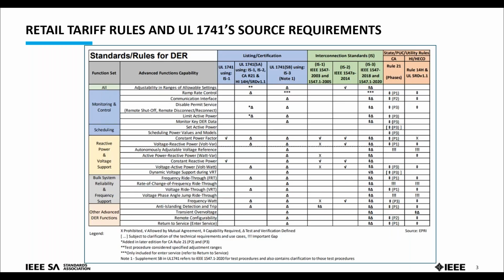Here's another tip on tools you can use. California and Hawaii actually preceded the update of 1547-2018 to add grid support capabilities. UL 1741 is the test and certification process published by UL as a standard, and certification testing can be done by any nationally recognized test lab to certify primarily energy storage inverters to 1547. The source requirement documents for California and Hawaii are public, and any energy storage inverter certified to UL 1741 SA has already been evaluated and verified to conform.